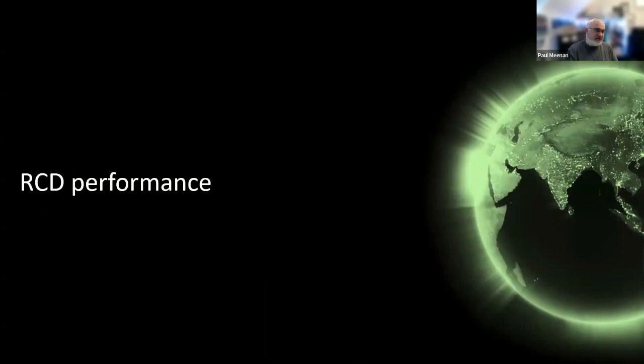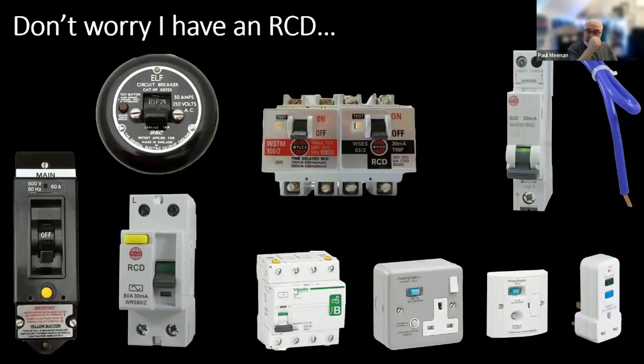So just on to one of the last bits, RCD performance. RCDs are a wonderful bit of tech. They've been out for many, many years, since 1939. Some of the examples where we had voltage earth leakage circuit breakers, VOELCBs, RCDs to BS 4293, BS EN 61008, and BS EN 61009. So we've gone on a huge journey of making the earth leakage protective device accessible to the market. And all it's ever done is improve safety. You know, it protects against fire and it protects against indirect shock. So it's a good thing if it works.